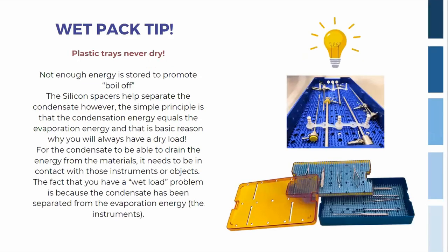So a wet pack tip: plastic trays never dry. There's not enough energy stored to promote boil-off. The silicone spacers help separate the condensate. However, the simple principle is that the condensation energy equals the evaporation energy, and that is the basic reason why you will always have a dry load. For the condensate to be able to drain the energy from the materials, it needs to be in contact with those instruments or objects. The fact that you have a wet load problem is because the condensate has been separated from the evaporation energy, the instruments or the device inside.